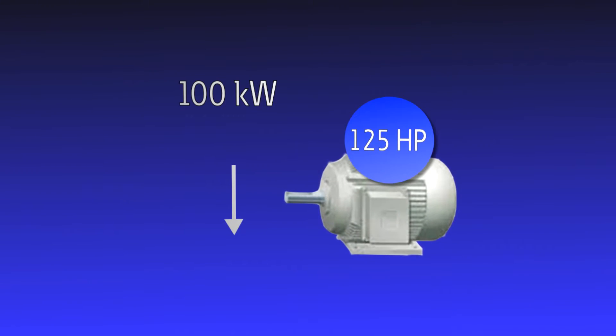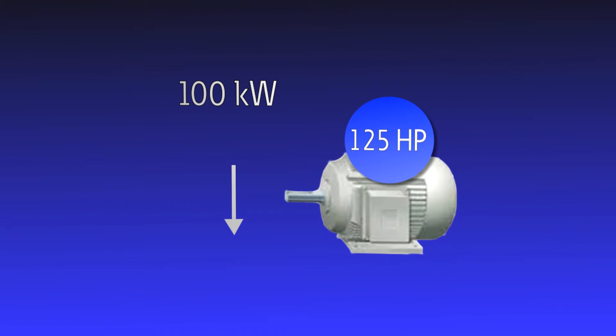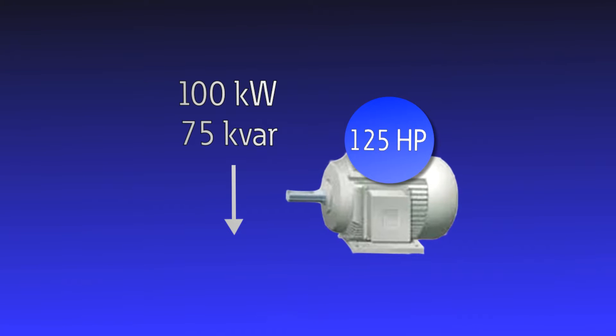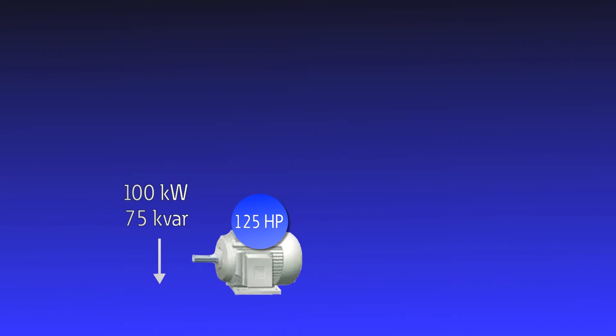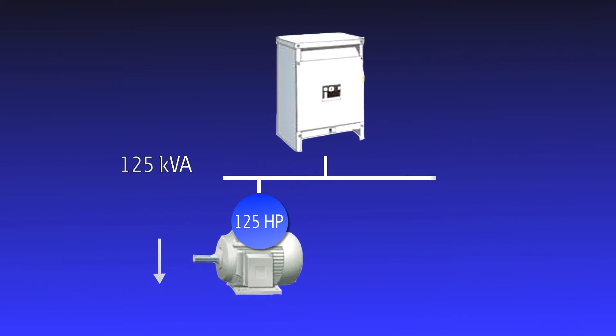Inductive loads require two kinds of power. They need real power, measured in kilowatts, to perform the actual work of creating heat, light, motion, and so on. They also need reactive power, measured in KVAR, to sustain their magnetic field. Together, these two make up apparent power.